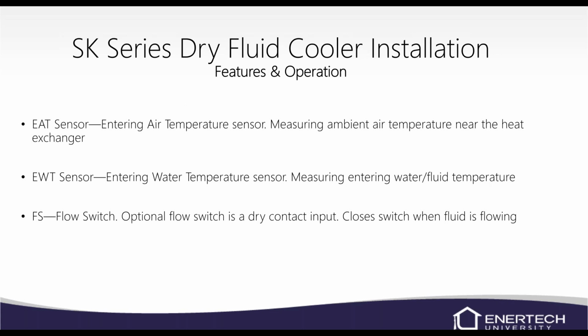There's an entering air temperature sensor. Again, that's measuring ambient air temperature near the heat exchanger. EWT sensor, which is the entering water temperature sensor, measures the entering fluid temperature. And then FS, which is your flow switch. There's an optional flow switch. It's a dry contact input, and basically it's a paddle switch, and it closes when the fluid pushes up against that paddle switch and closes the circuit. Just like any of our other flow switches that we have in our units.